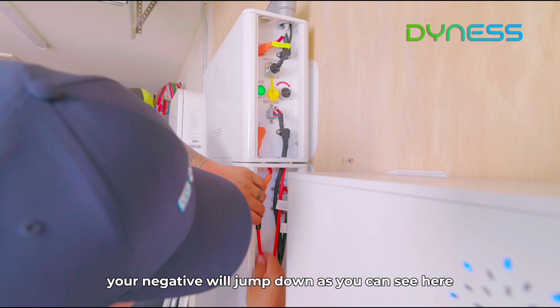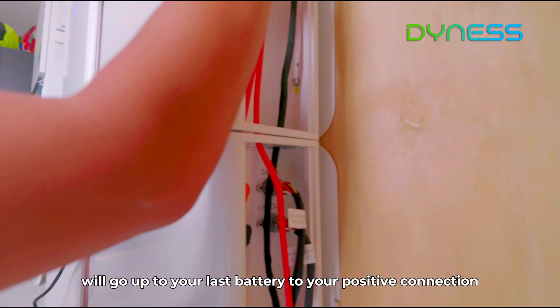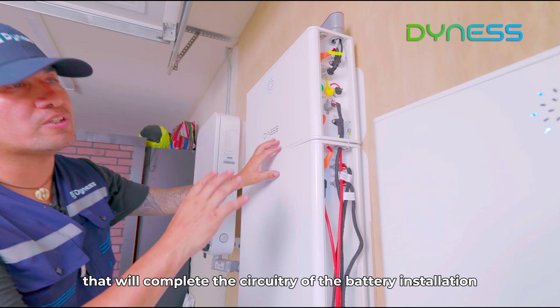Make sure you want to comply to all the NEC code. Goes over to your third battery, going up to your positive connection. And then your negative connection will go up to your last battery to your positive connection. And then your negative connection, this is the one that we need to make sure we're installing correctly, because this is the jumper that goes from here all the way back up, down and up to your first battery BDU. And that'll complete the circuitry of the battery installation.